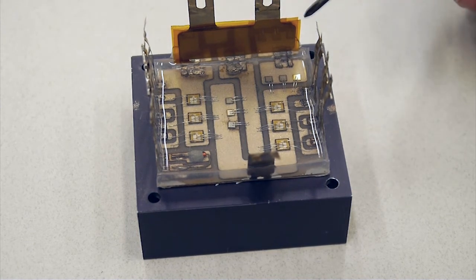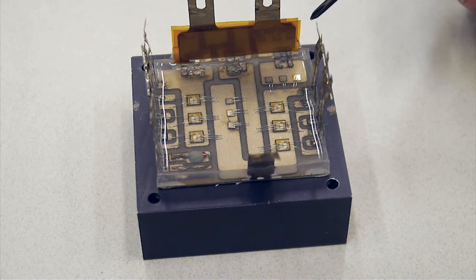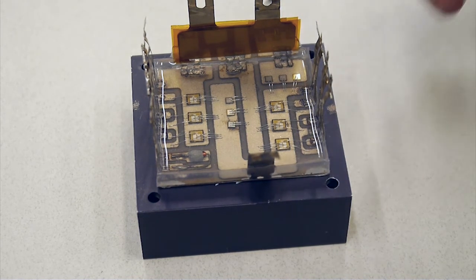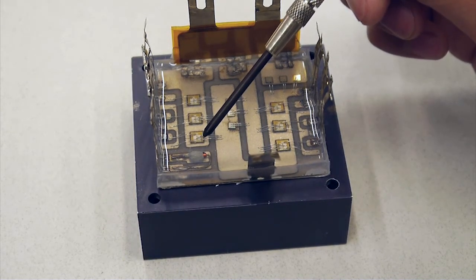On this side of the module, we can see this is a DC bus bar in a laminated structure. This is also for the purpose of reducing the switching loop inductance. On the bottom left corner, you can see this is a thermistor we use to measure the module temperature.